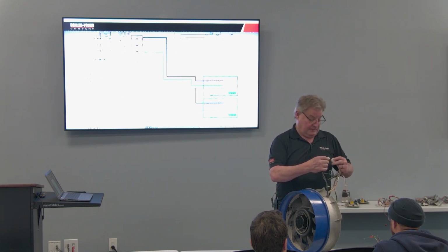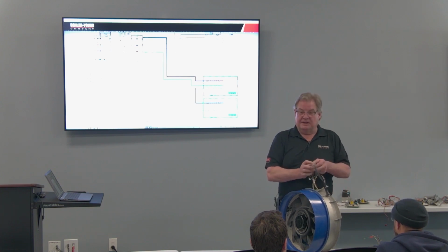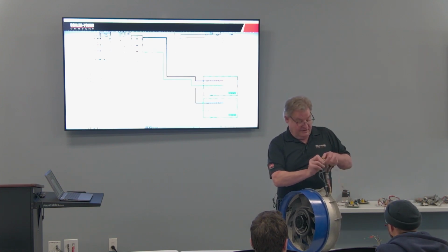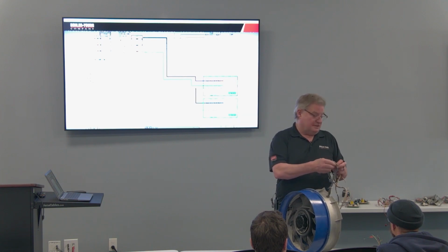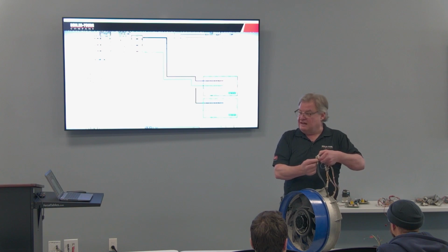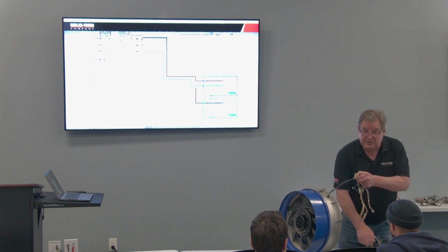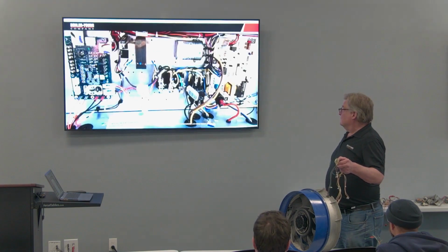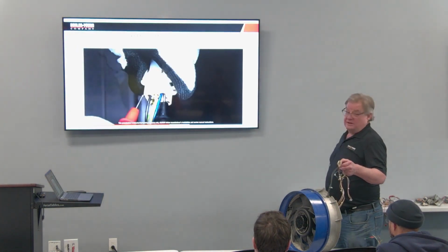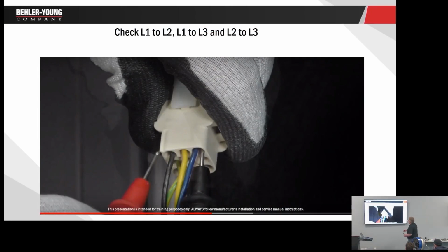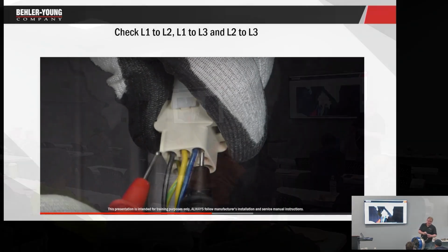So, meter leads this side. If I flip this over, here's my black and yellow. Black is L1, yellow is L2. I'm going to put my meter leads in the plug side, the wire side of this plug, and check for my line voltage. So if I check here, yeah, right there. Now I'm seeing what the motor's getting, because what if these contacts are damaged? I've had it happen. So we're going to check it here, because now I can see that motor's really getting 230 volts, right? So I know this contact is good. I know this contact is good. And if I don't have power here, I'm not going to have it here either. So if I don't have it here, I might have to backtrack. But I'm going to check it right here.